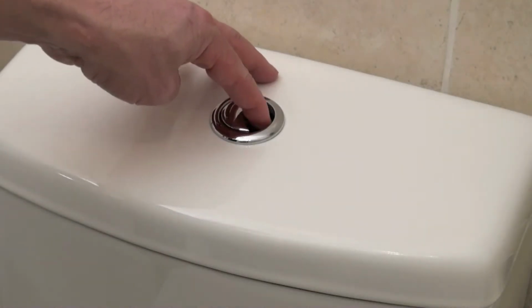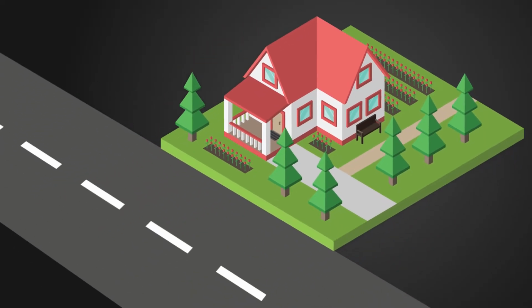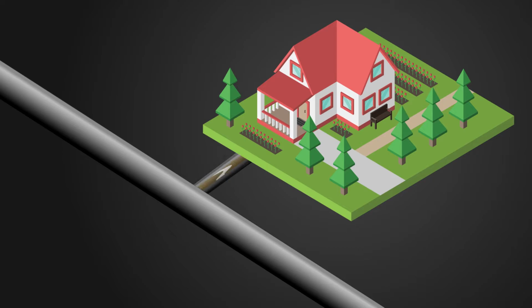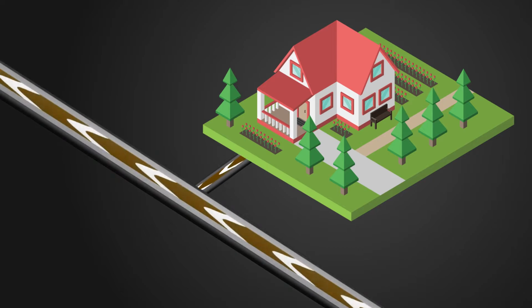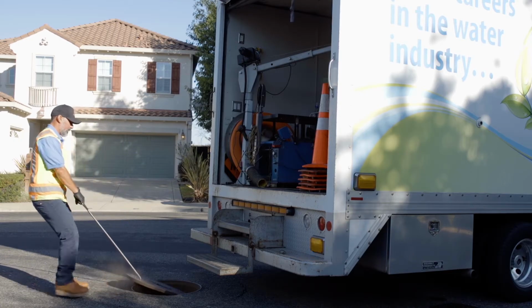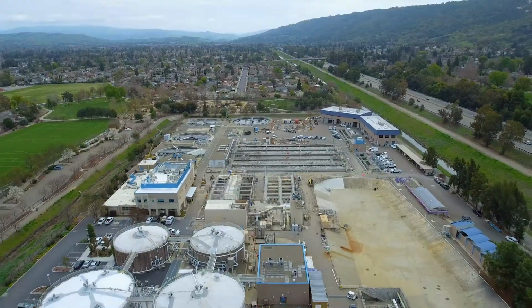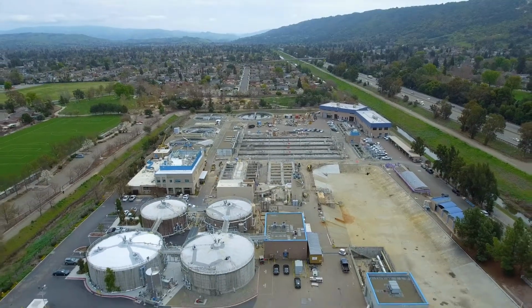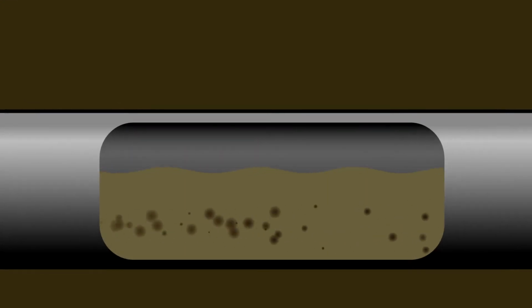Well, wastewater collection starts out at the home. So as people flush their toilets and take showers, that water runs out into the sewer pipe or collection system pipe in the street. By the time that water gets to the treatment plant, it's running in 48-inch or 4-foot diameter pipes traveling at an average velocity of 2 feet per second. So that's enough to keep everything in suspension.